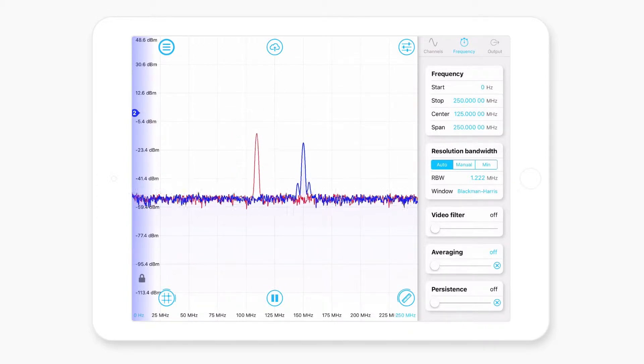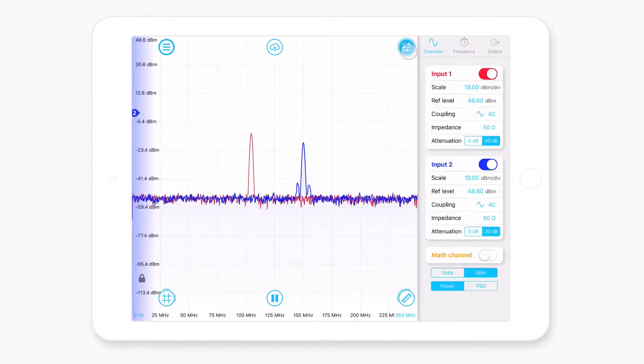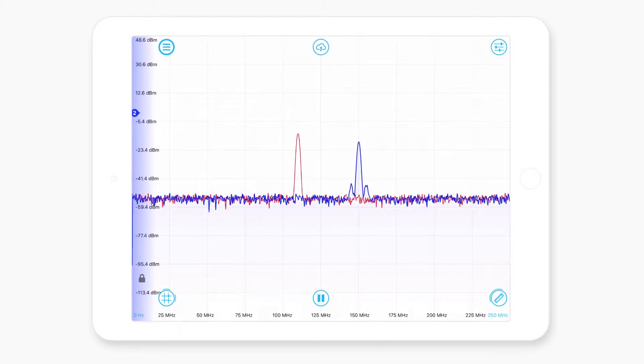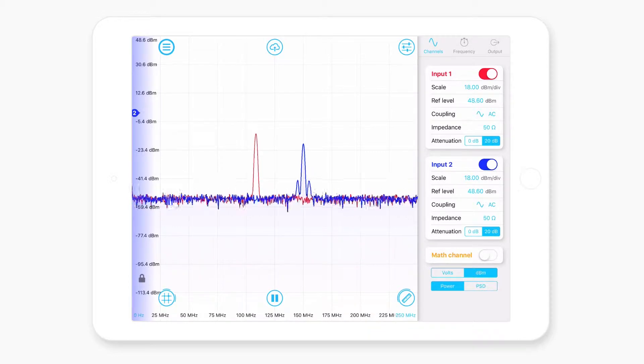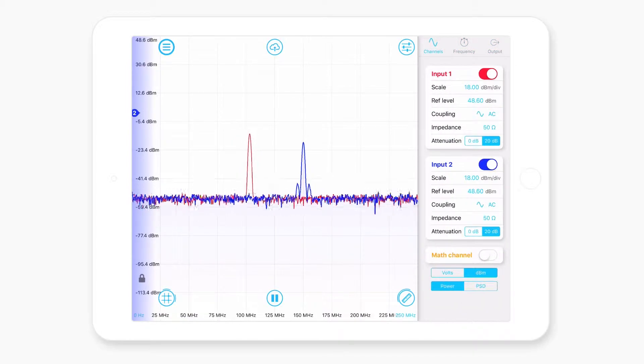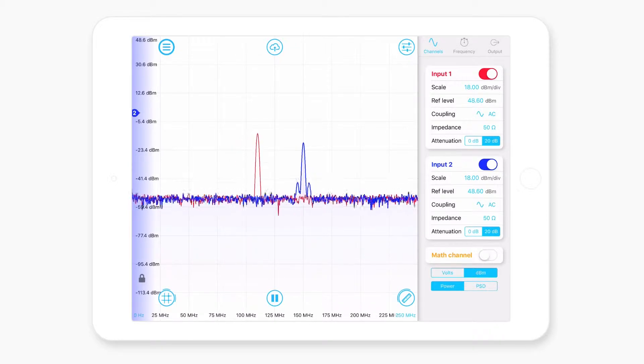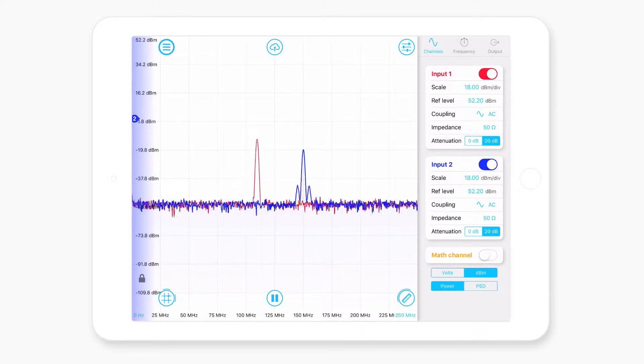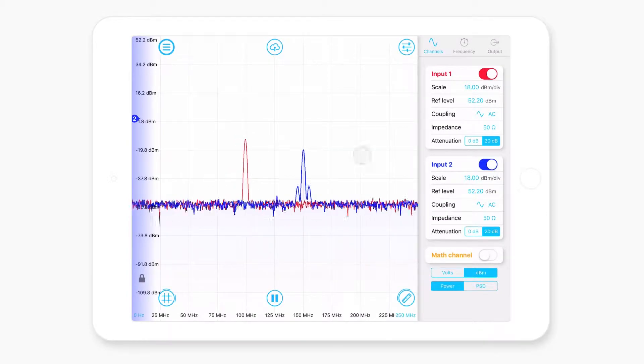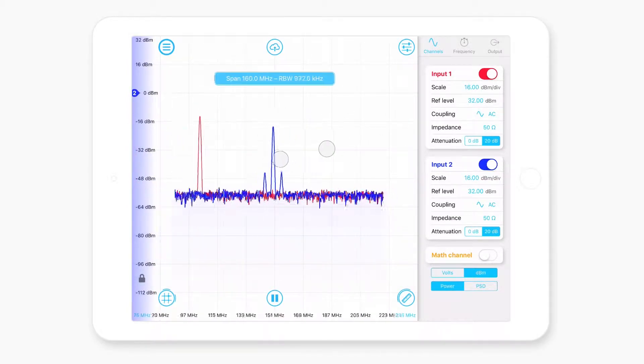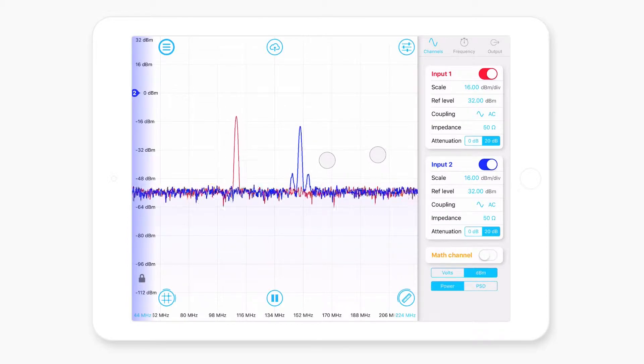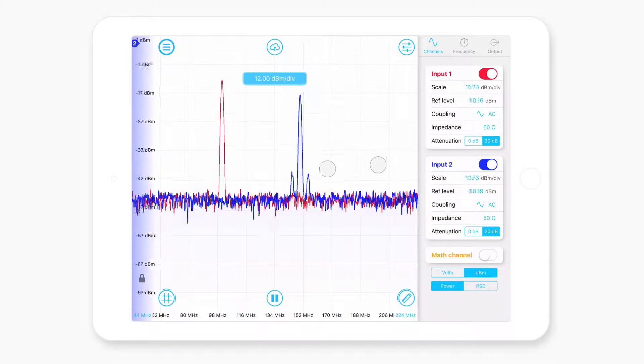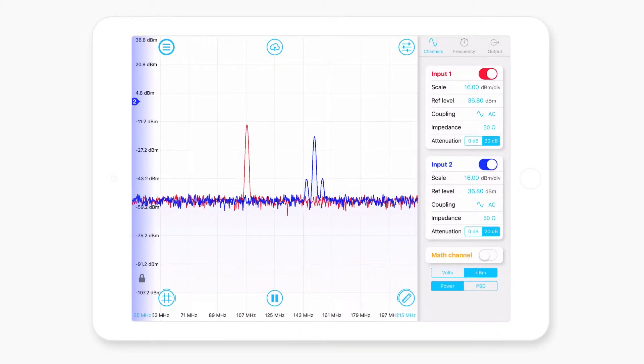All right. So the next icon that is worth noting is the hide and show the settings panel icon. So this is this one at the top right here. So if you didn't want to see all the settings, you can just hide it. This gives you maximum screen real estate for looking at your traces. To reveal it, you basically just tap it. And what it does is it brings up this little measurements panel with three different tabs. The first tab is basically how you set up each of the different inputs. So we can select things like voltage scale, the reference level. These are generally actually the scale and the ref level are most easily configured using gestures. So you'll notice that I can pinch and zoom and I can pan around and I can pinch sideways to change the span. And but the other thing you can do is if you put two fingers on the screen and then move up, it'll zoom all the way out. And if you pull them down, it'll zoom in. So that's a nice quick gesture for very quickly changing the scale and span.